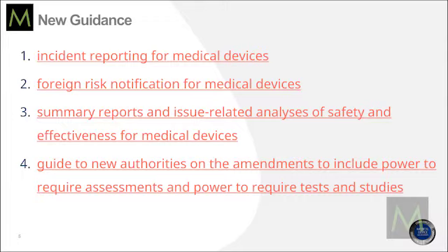The second guidance document is foreign risk notification for medical devices. If you have products in other countries, you used to not have to report to Health Canada unless you were implementing corrective action. Now they're making it more elaborate as to what things trigger you having to report a change or problem with your device. Half of the new law went into effect in June and the other half goes into effect December 23rd. You should already have updated your procedure to say incident reporting and to notify Health Canada of changes that occur in other countries.